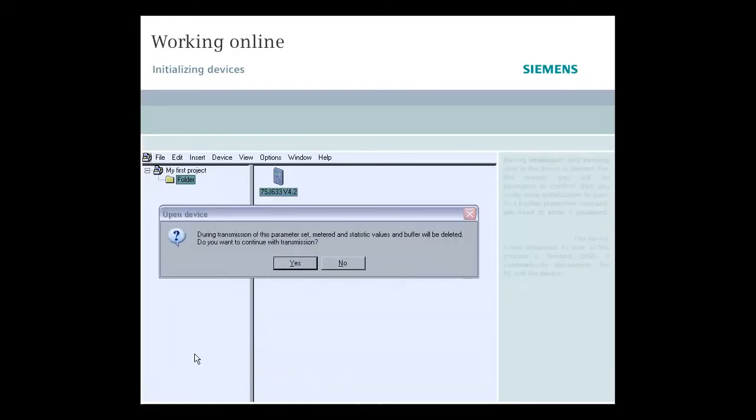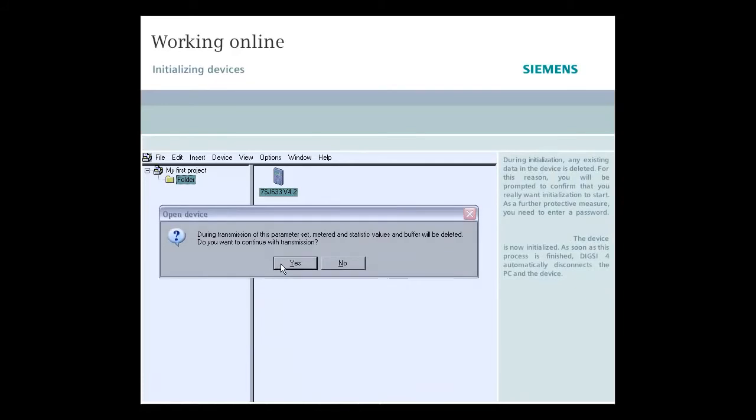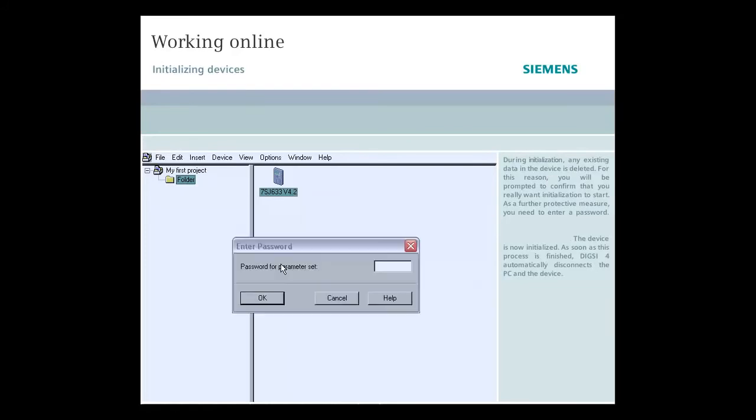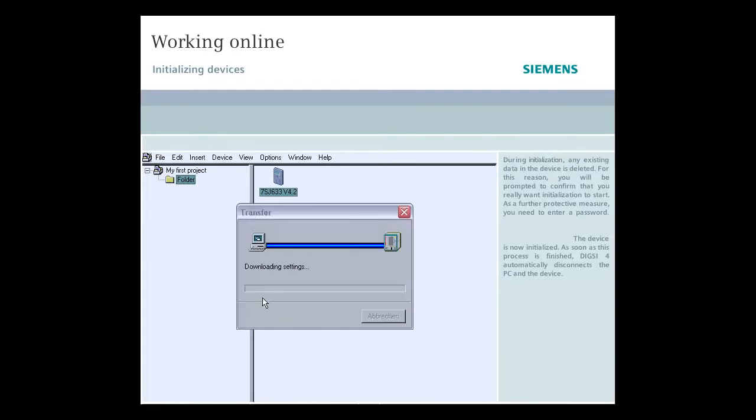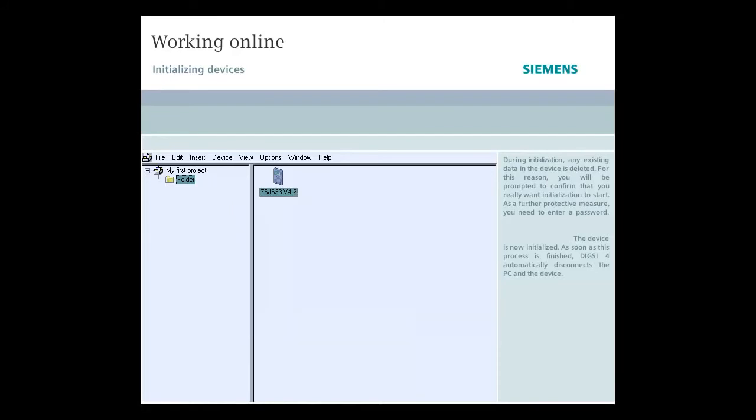During initialization, any existing data in the device is deleted. For this reason, you will be prompted to confirm that you really want initialization to start. As a further protective measure, you need to enter a password. The device is now initialized. As soon as this process is finished, DIGSI 4 automatically disconnects the PC and the device.